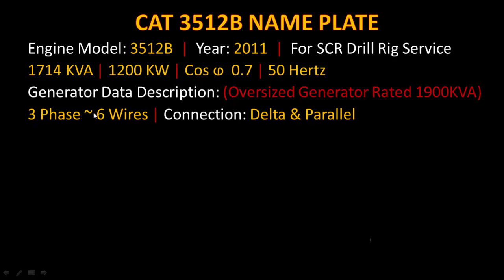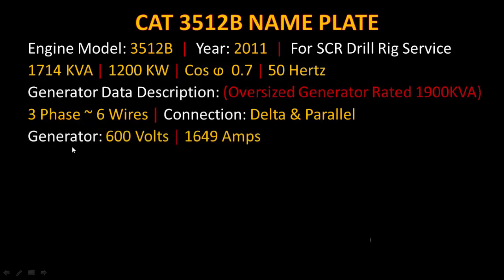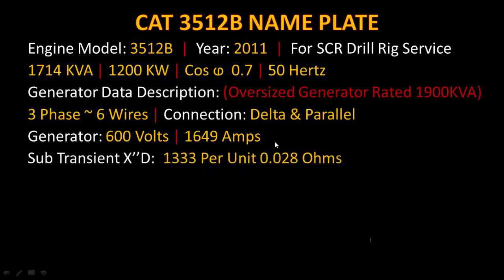Looking at the generator data description: the generator is oversized, rated at 1900 kVA. It is three-phase sinusoidal with a total of six wires. The winding connection is in delta and also in parallel. The output voltage is 600 volts AC, and the total current is 1649 amperes.